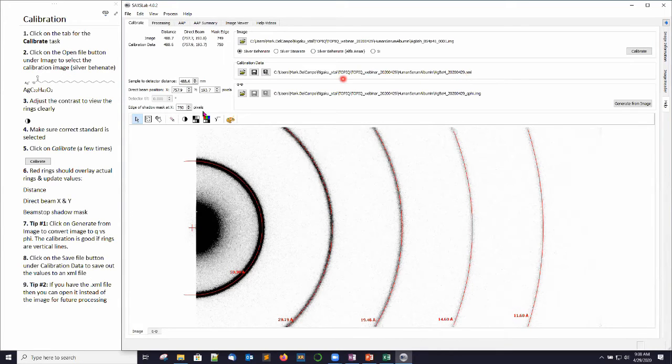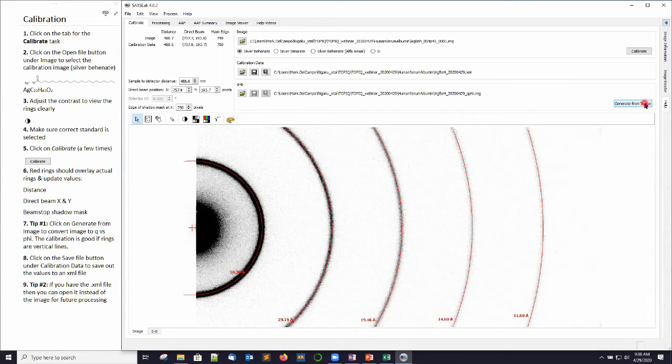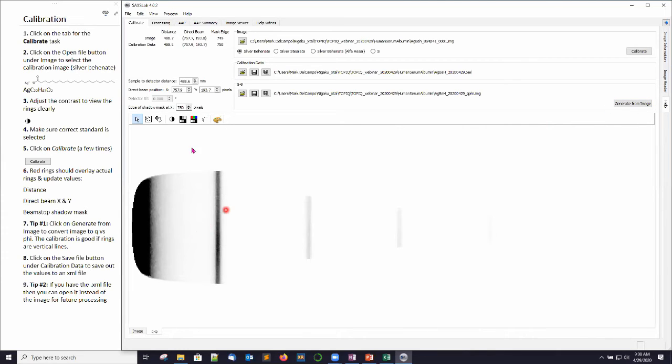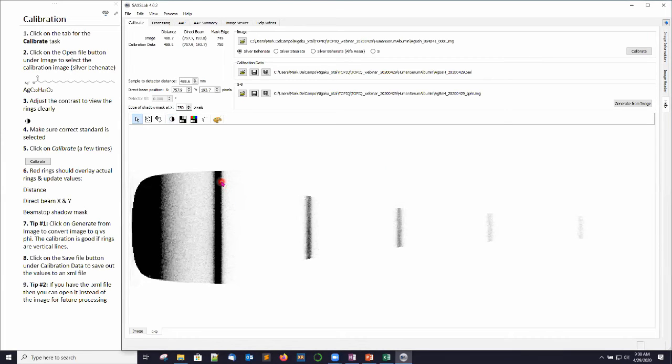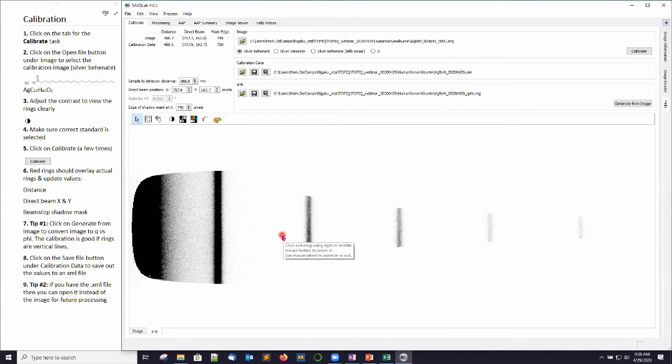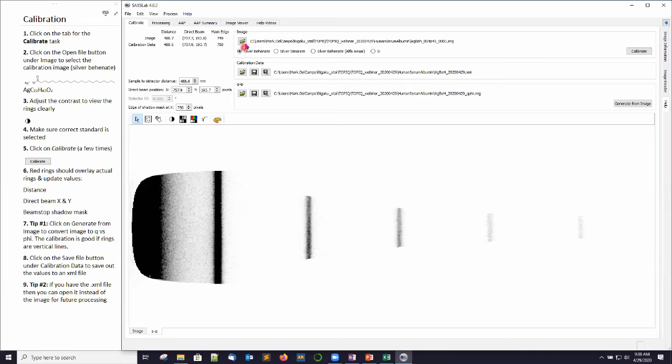So this bit of four numbers is the calibration information. And so once you have these values, we can save out this stuff by clicking on the save file icon under calibration data. We click that, and we save out these values to an XML file. So let's go over my two tips now. If you want to check whether this calibration has run successfully, one thing you can do is click on this generate from image button on the right side and convert from a SAXS image to a Q-Phi image. And in this conversion, since all of these powder rings occur at the same resolution, all the rings end up as straight lines in this Q-Phi image, then you know the calibration has run correctly. My second tip is that once you've generated this XML file, if you're going to process data that uses the same calibration in the future, instead of opening the image here, all you need to do is open up this XML file and you'll be good to run processing with SAXSLab.